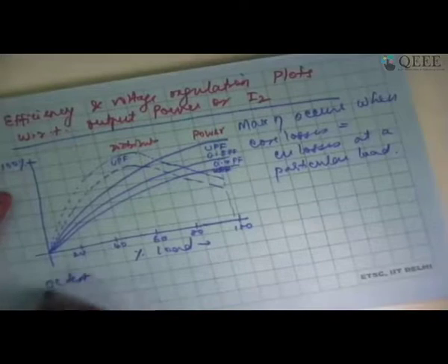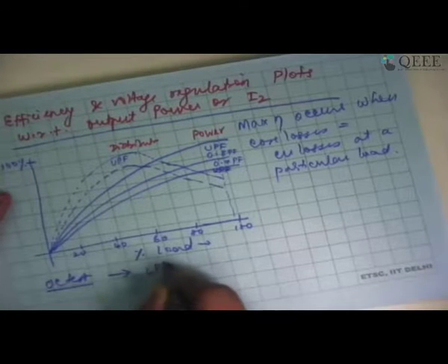That's the reason. The other question that has come up is, what is the power factor of the wattmeters in both LV and HV respectively? See, in open circuit test and short circuit test, you can say what kind of wattmeters you are going to use. In open circuit test, normally we tend to use a LPF wattmeter.